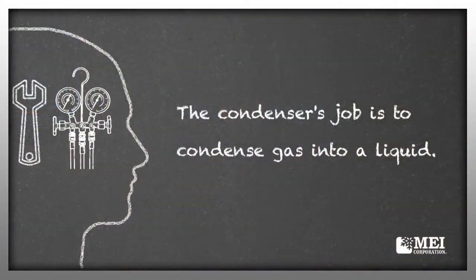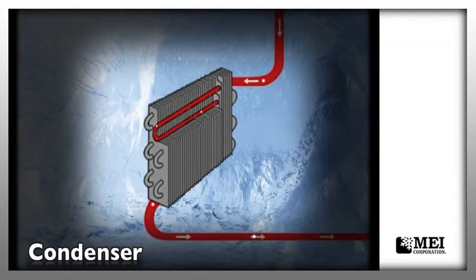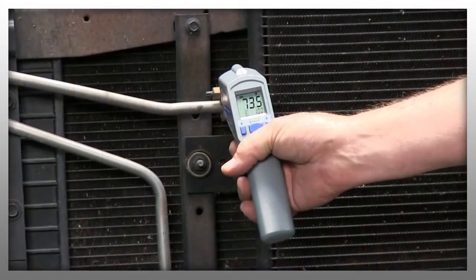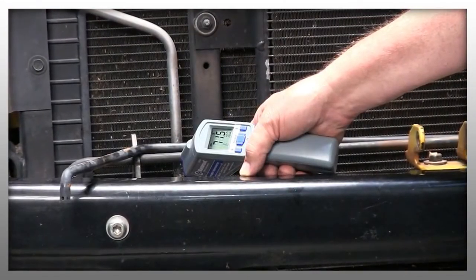The job of the condenser, as its name implies, is to condense this gas into a liquid. Like a radiator system, it'll drop the temperature of that fluid — it starts in as a gas and comes out as a liquid. You'll lose somewhere between 16 and 26 degrees. If you take your temperature gun, shoot the line coming in and going out and see a 10, 15, or even 26 degree drop, that's very normal. If you see it freezing up, if you see frost on your condenser, then you know you have a restriction at that point — and that's one place you need to check.